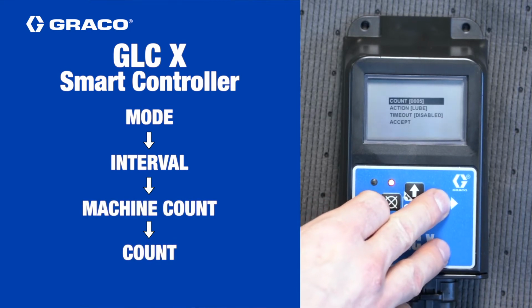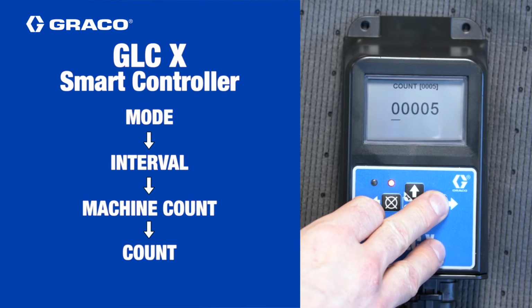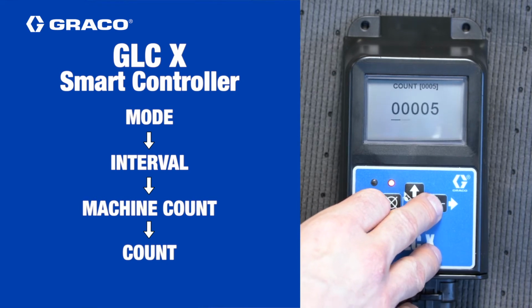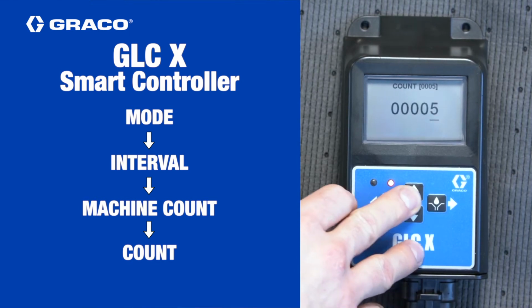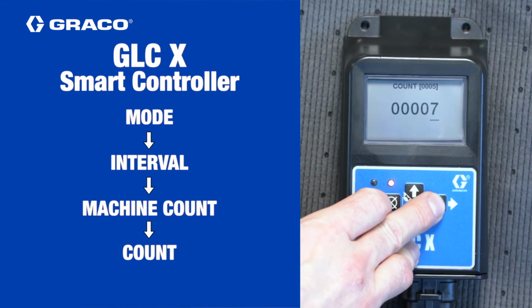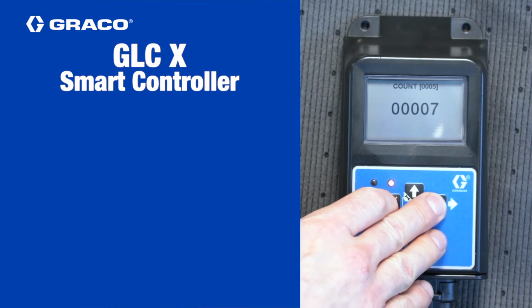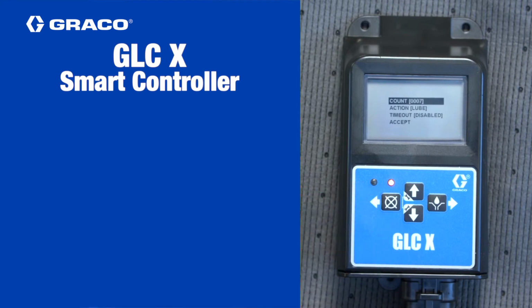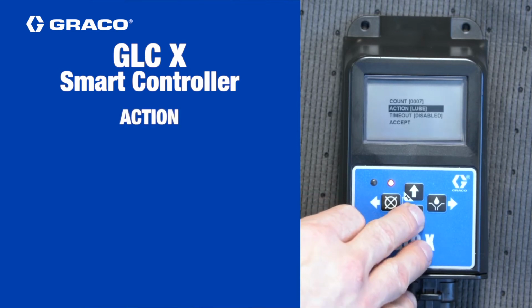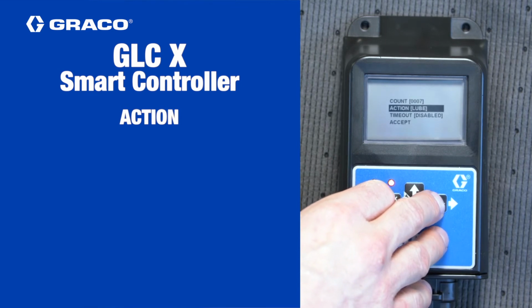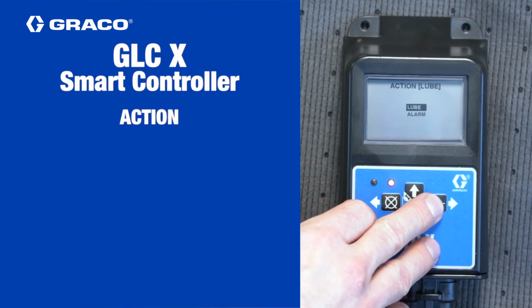Select Count and press the right arrow key, then set the number of machine counts required by the application, and press the right arrow key once more to return to the previous screen. Use the arrow keys to select Action, and then choose between Lube and Alarm. This setting determines what the controller will do when time expires.